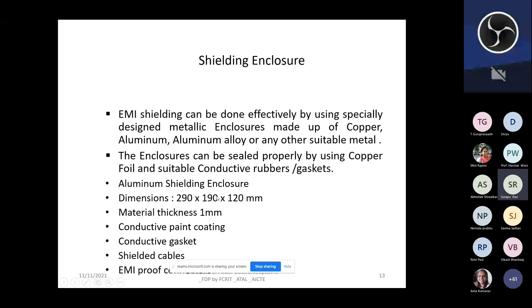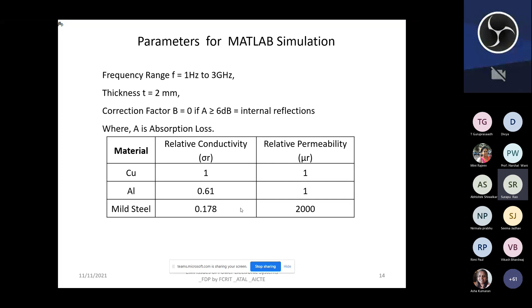Initially we have done it with 1 mm thickness, but it was not sufficient. So we have now gone for thickness T equal to 2 mm, right? So these are the parameters of copper, aluminum, and mild steel: relative conductivity and relative permeability. You will see that copper is a better conductor. Relative conductivity is 1, whereas aluminum has 0.61, lesser than copper. But still, aluminum is a better choice because of the anti-rusting properties and other things which we have discussed. Now these are the simulation formulas which one has to use for the enclosure.